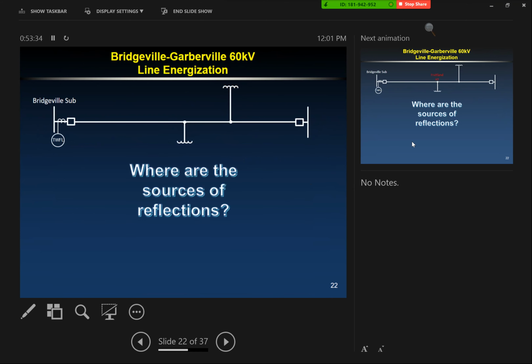So what are our sources of reflection on a line like this? Pretty much anytime you have a change in characteristic impedance on your line. So here's your first change in characteristic impedance. If you start at the Bridgeville end, you have a characteristic impedance of the line, then boom, you have a junction point, two parallel lines. That would look like half of the impedance of the line. That's definitely a change in characteristic impedance.